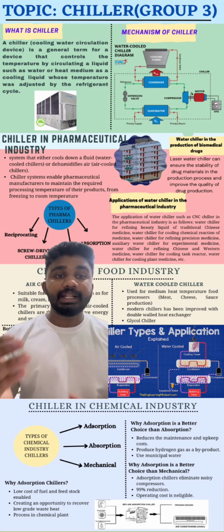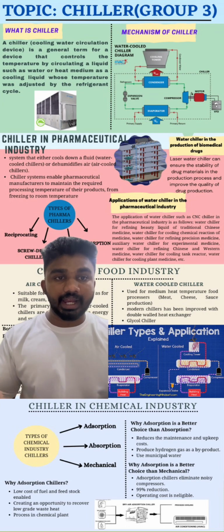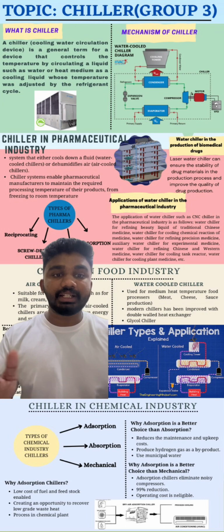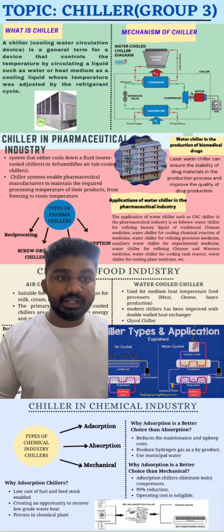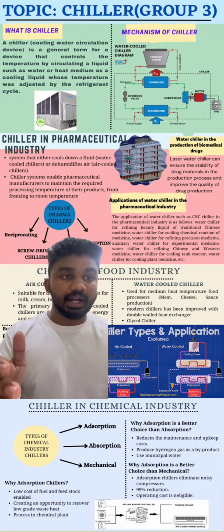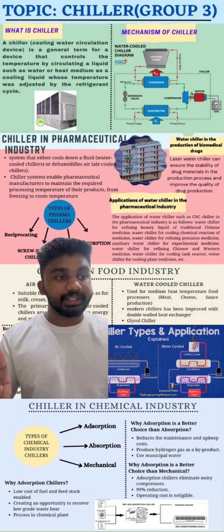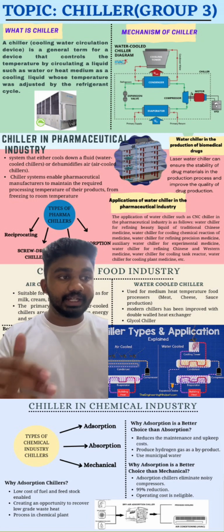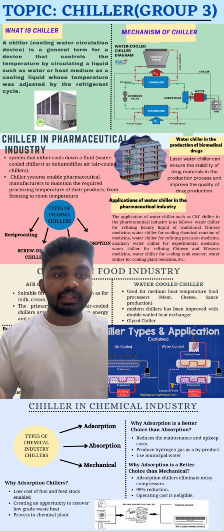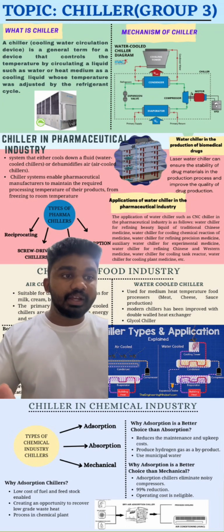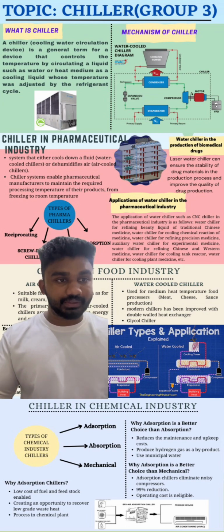Adsorption chillers use municipal water as the refrigerant and solid silica gel as the desiccant. The next part is why an adsorption chiller is a better choice than a mechanical chiller. Adsorption chillers eliminate noisy compressors, high pressure refrigerant systems, high amperage electrical connections, refrigerant monitoring and alarm systems, and also high maintenance costs.